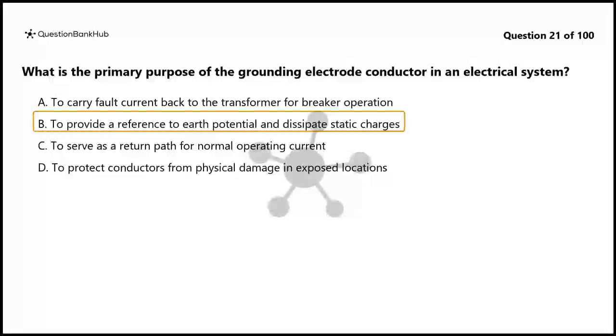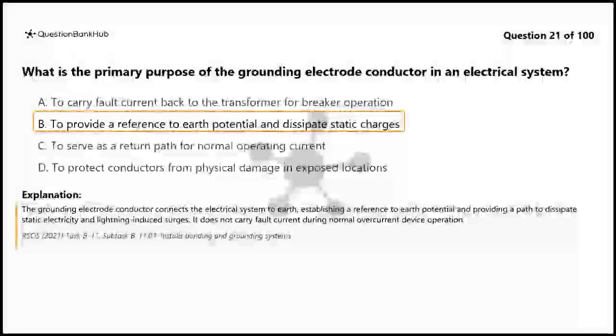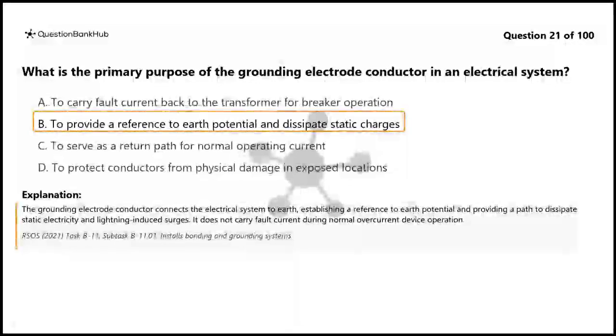The correct answer is B. To provide a reference to earth potential and dissipate static charges. The grounding electrode conductor connects the electrical system to earth, establishing a reference to earth potential and providing a path to dissipate static electricity and lightning-induced surges. It does not carry fault current during normal overcurrent device operation.